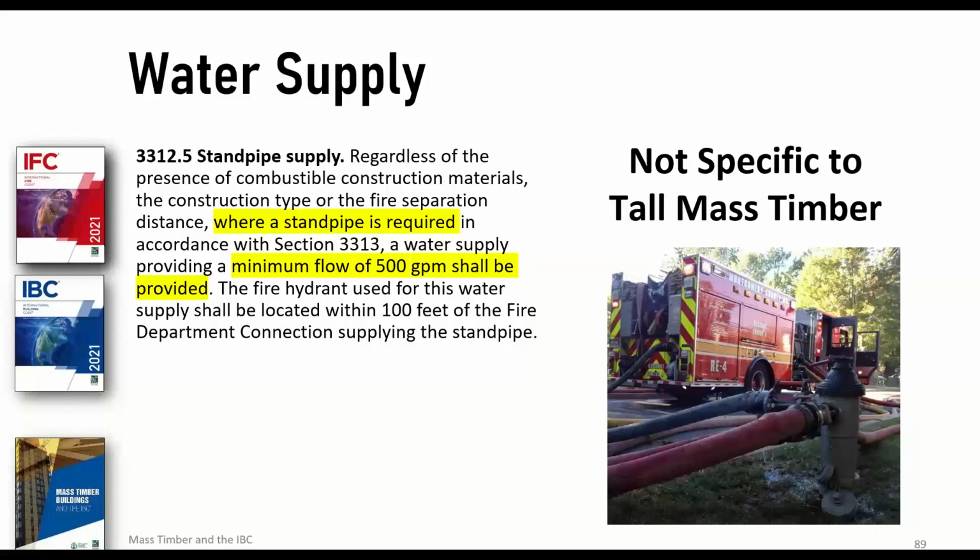Construction fires have just been a problem recently, and one of the issues is that water supply infrastructure is not always complete prior to vertical construction of the building. The lack of a reliable and sufficient water supply has contributed to significant fire loss during construction site fires. The fire service can't suppress a fire of any significant size without a reliable water supply.